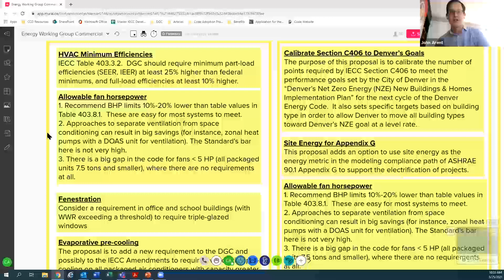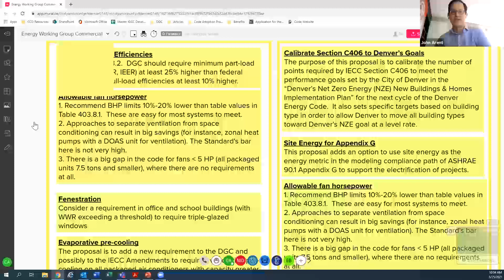allowable fan horsepower. There's fan power requirements for commercial systems, and the recommendation, again, some of these are aspirational. So this one would be also for the Green Code potentially. For systems that run, especially in commercial buildings that run continuously to provide ventilation as well as cooling and heating, the fan power really has a big impact on energy use. So the recommendation here is to set brake horsepower limits 10 or 20% lower than the tabulated values in IECC. This certainly depends on the design of the system, the ductwork, et cetera. But my finding is that for many of these types of buildings, they can exceed the minimum requirements set forth in the base standard.